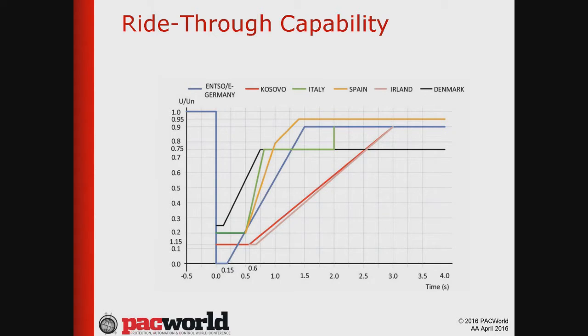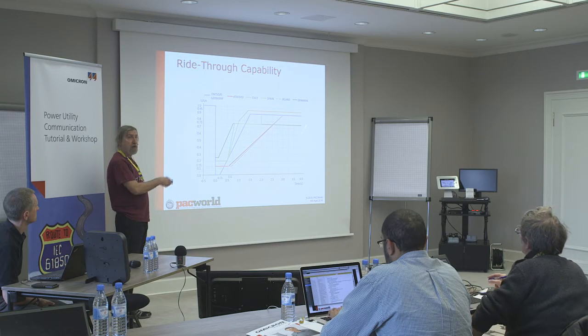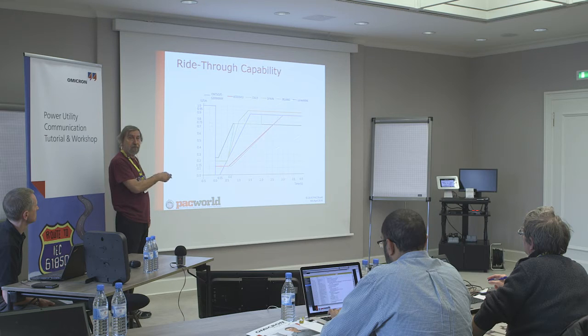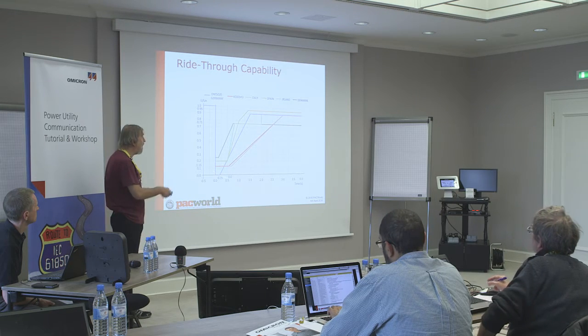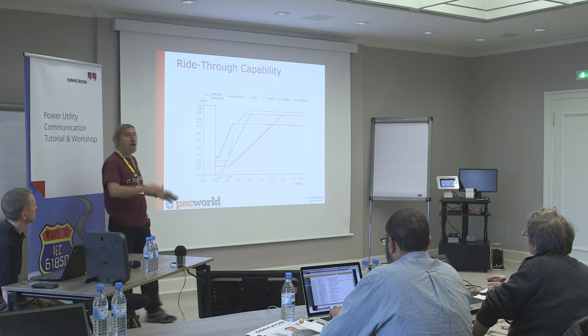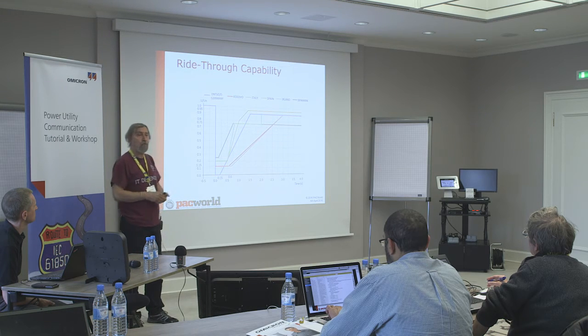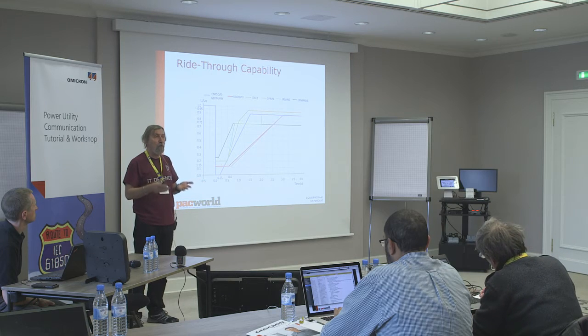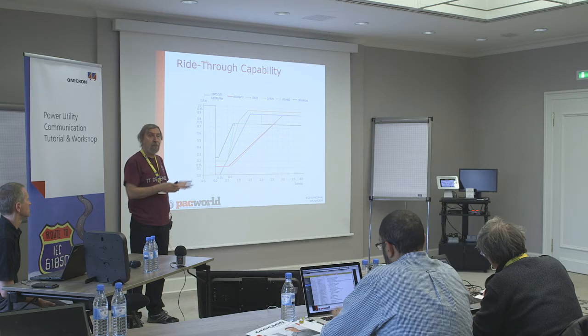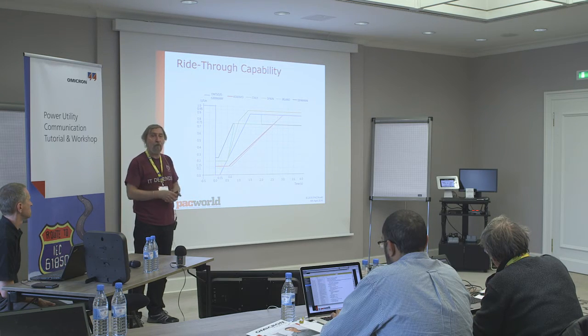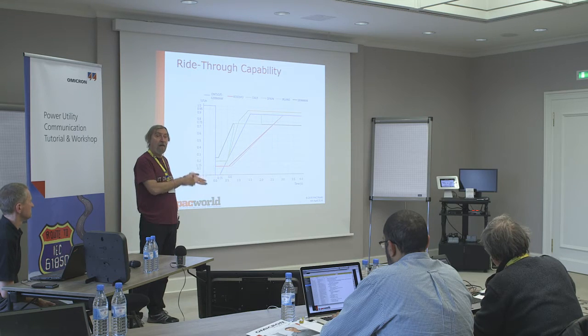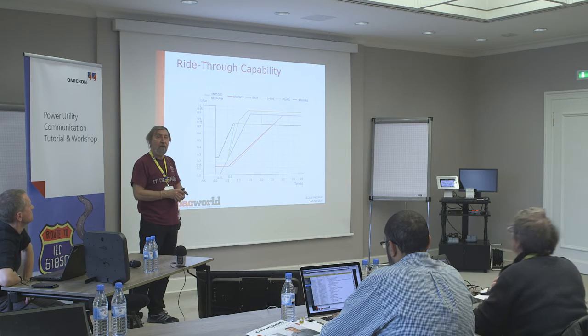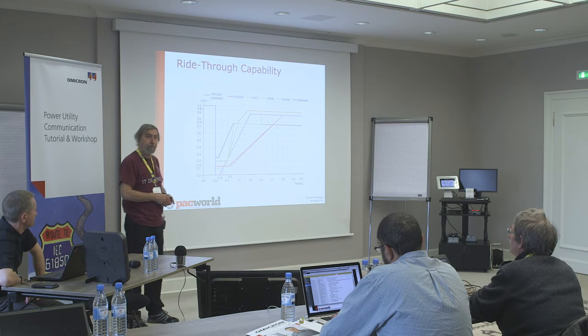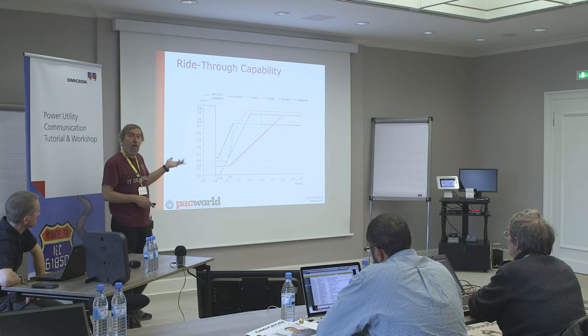And because of that, many countries have introduced what is called a ride-through capability curve. What does it mean? It means that there is an area within which the wind generator should not disconnect from the system. It should withstand this voltage sag, and then there is an area that if it goes below a certain level and longer than a certain duration, it is allowed to trip. However, imagine if you have a country that has 40 or 50% of the electric power generated by wind generators, and you have an area that is affected by a short circuit fault. This short circuit fault may lead to the loss of a large number of wind generators that is going to present a stability problem. So now we need to start thinking how we can solve this problem.